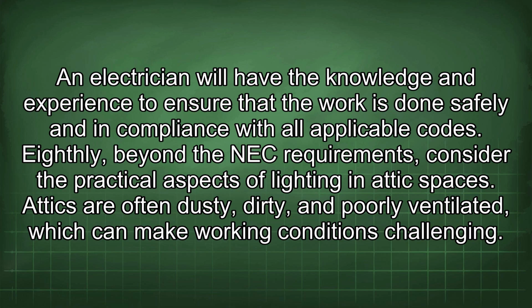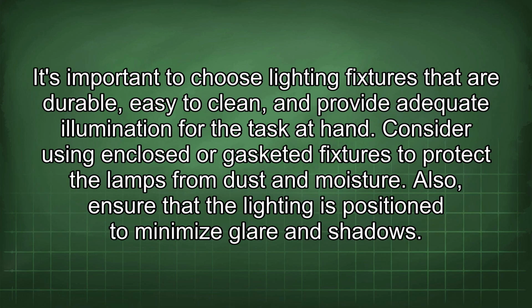all applicable codes. Eighthly, beyond the NEC requirements, consider the practical aspects of lighting in attic spaces. Attics are often dusty, dirty, and poorly ventilated, which can make working conditions challenging. It's important to choose lighting fixtures that are durable, easy to clean, and provide adequate illumination for the task at hand. Consider using enclosed or gasketed fixtures to protect the lamps from dust and moisture. Also, ensure that the lighting is positioned to minimize glare and shadows.